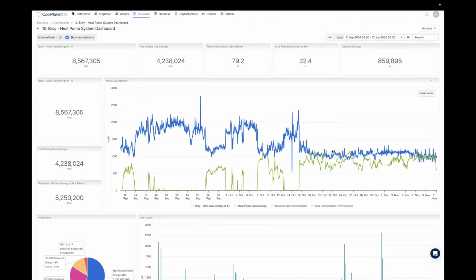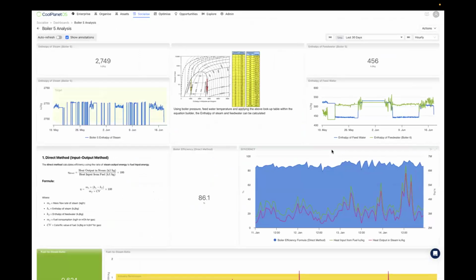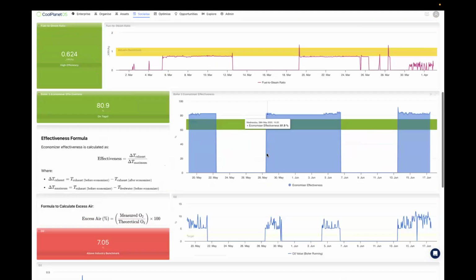This particular solution didn't achieve the exact savings that were theorized. We were around 20 to 30% under expected savings. Even though it achieved some really good, healthy savings, we were still below the target savings. And that's why it's so important to take a holistic view of the impact when you install new technology, new equipment like a heat pump, and how it affects other systems on the site. So once we didn't achieve those savings, we drilled down further into one particular boiler on that system.